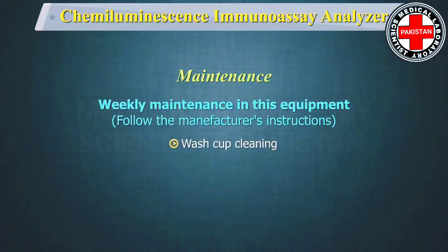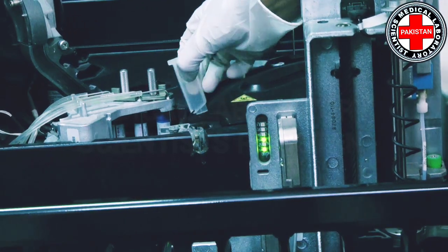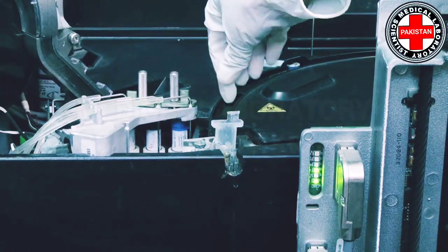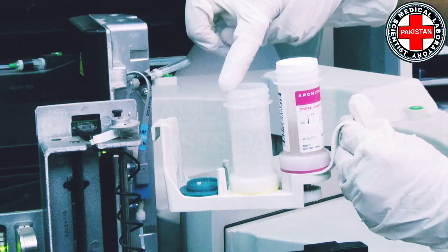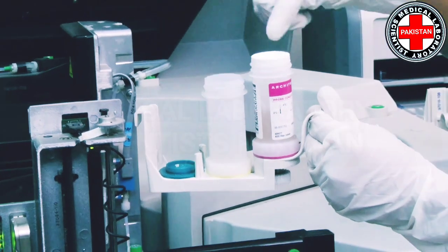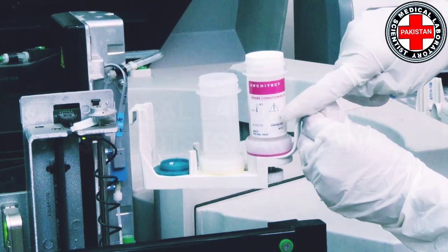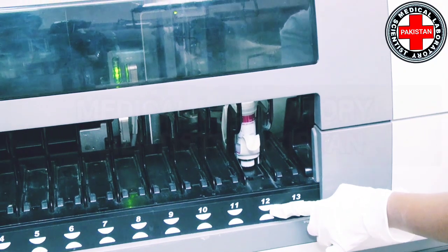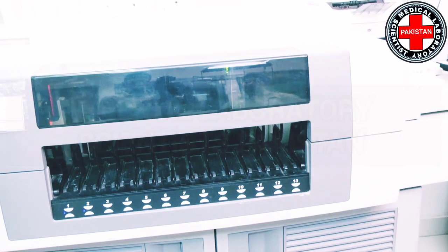Wash cup cleaning: The wash cup is where the probe is washed and leaves debris, so it needs to be cleaned manually. Remove the wash cup, clean with distilled water, and replace gently. Wash zone probe cleaning is done with 0.5% hypochlorite and a probe conditioning solution to remove residual hypochlorite. Place both solutions on the reagent carrier, load it on the system, and the cleaning process will commence automatically on giving the command.